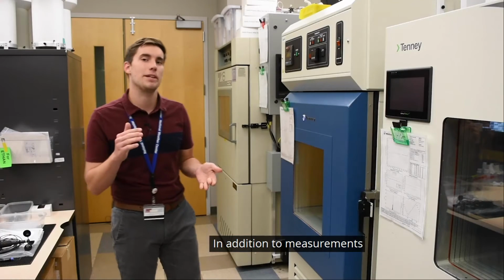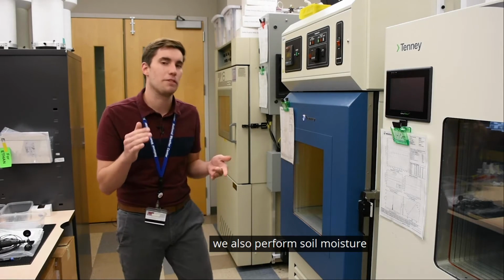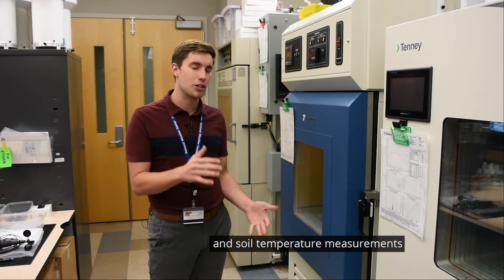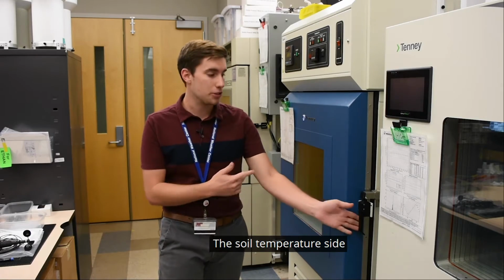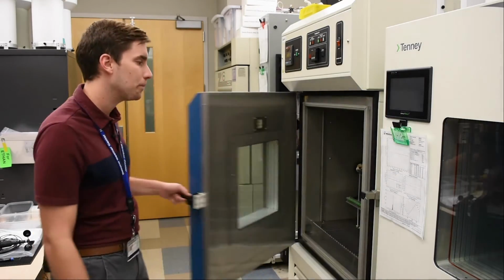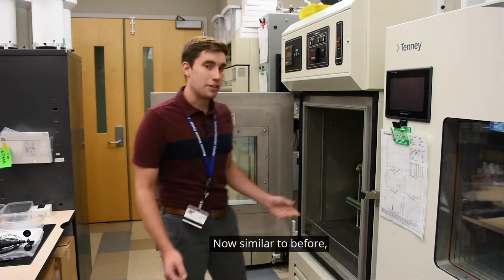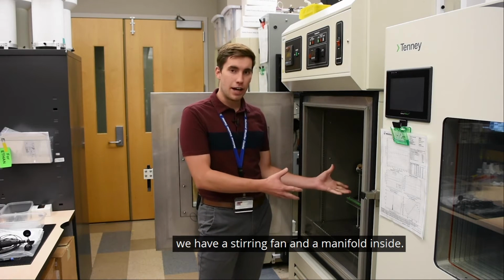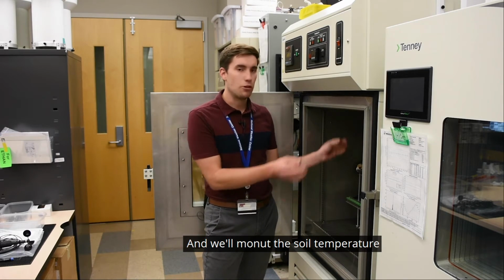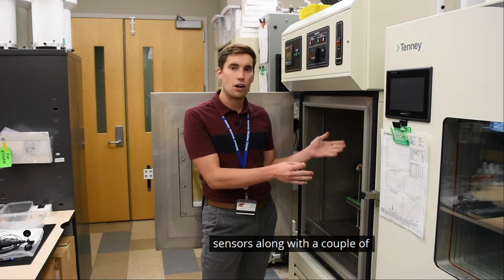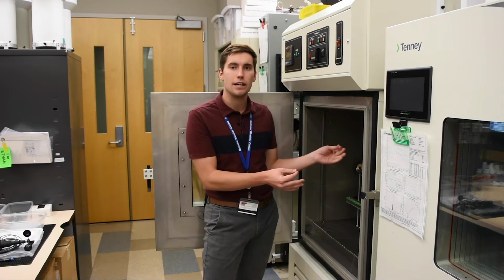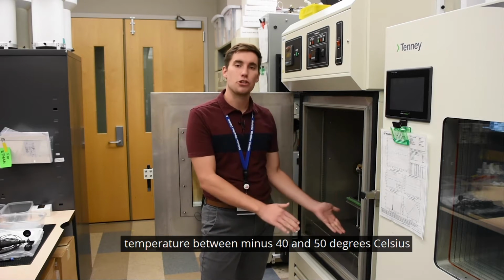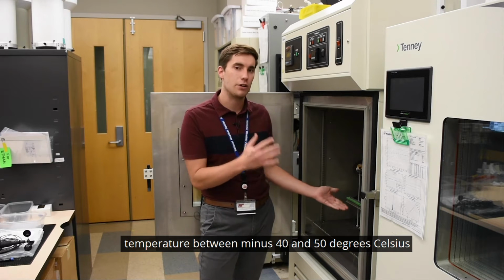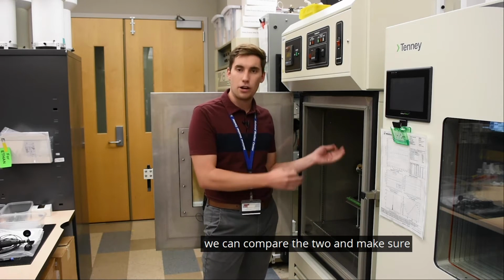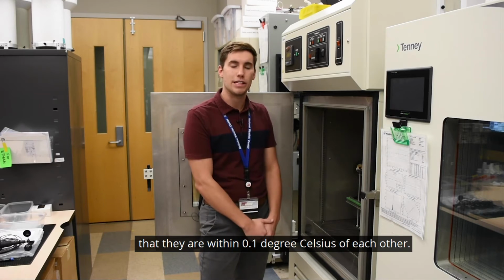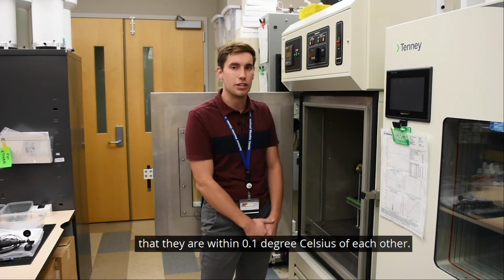In addition to measurements above the surface, we also perform soil moisture and soil temperature measurements below ground. The soil temperature side is performed in this chamber here. Now, similar to before, we have a stirring fan and a manifold inside, and we'll mount the soil temperature sensors along with a couple reference sensors inside. And then after we change the temperature between -40 and 50 degrees Celsius, we can compare the two and make sure that they are within 0.1 degrees Celsius of each other.